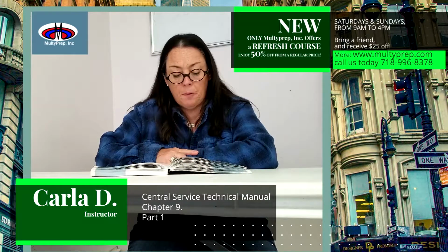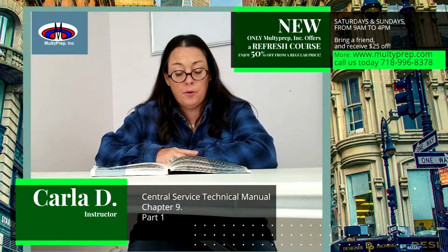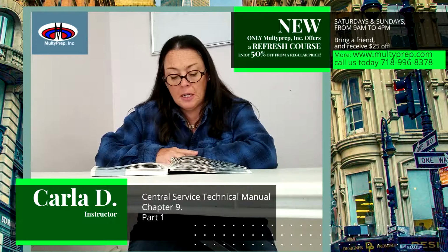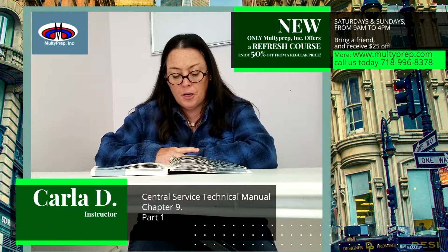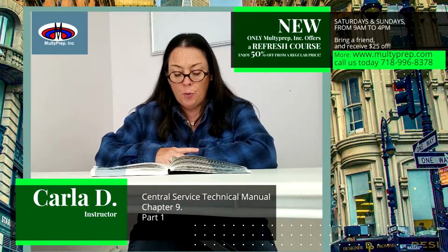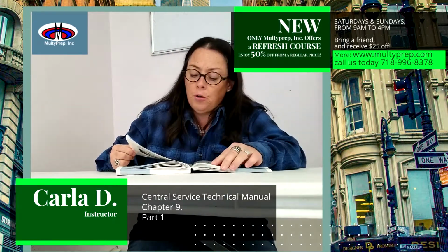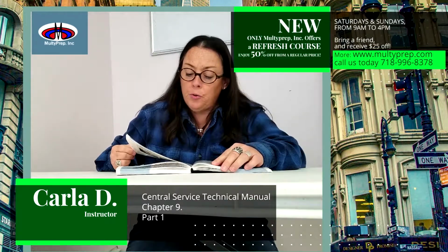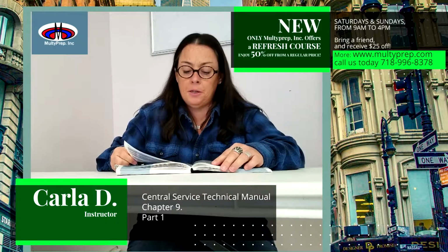Glutaraldehyde should be used in a separate designated area. Any room where glutaraldehyde is used should be well ventilated with a minimum of 10 air exchanges per hour. When a dedicated area is not available, glutaraldehyde disinfection may be performed at an enclosed workstation. These self-contained workstations manage airflow and reduce exposure to fumes. Figure 9.12 shows some examples of these stations. Unused glutaraldehyde solution should be stored in a cool, secure location in tightly closed, properly marked containers labeled with the activation date.